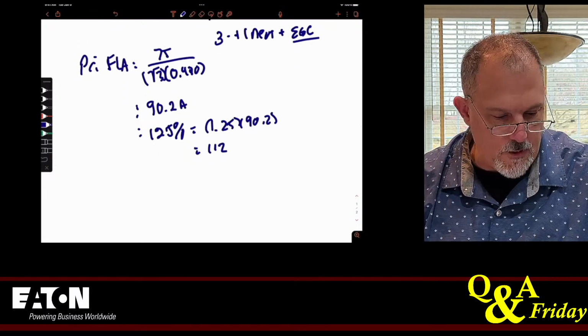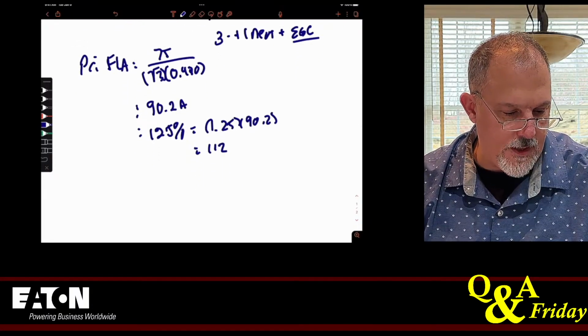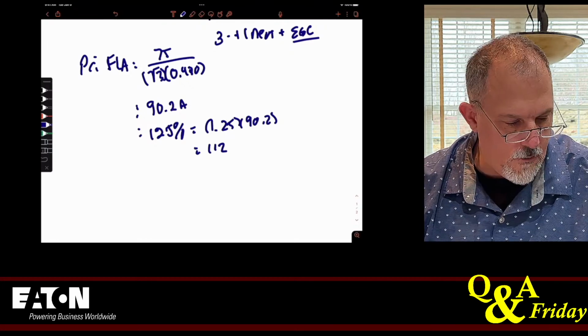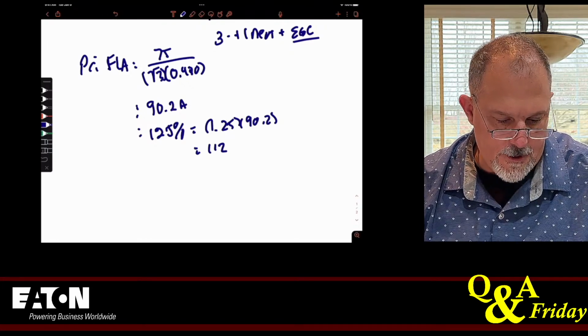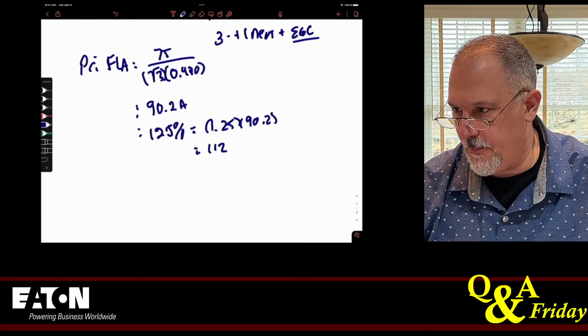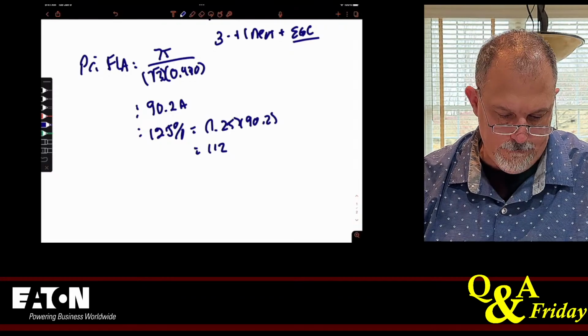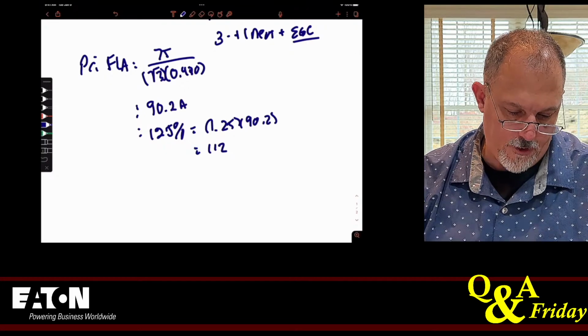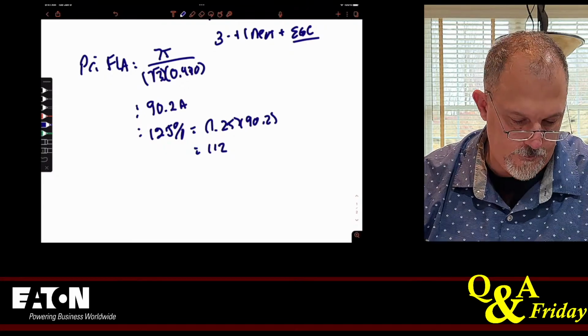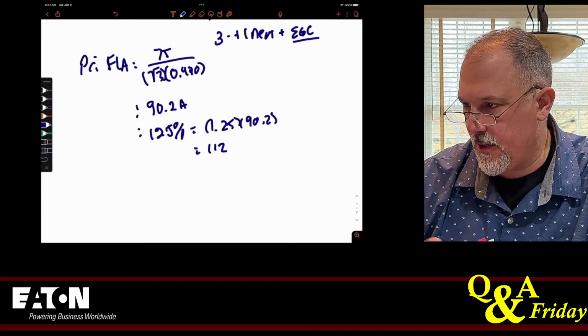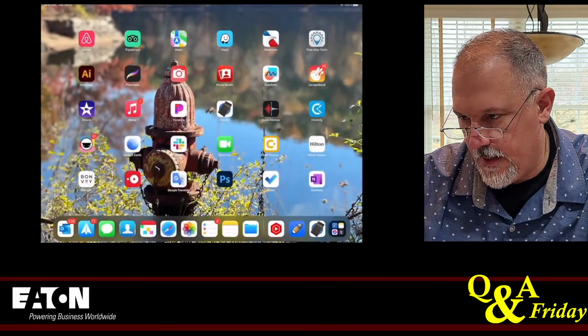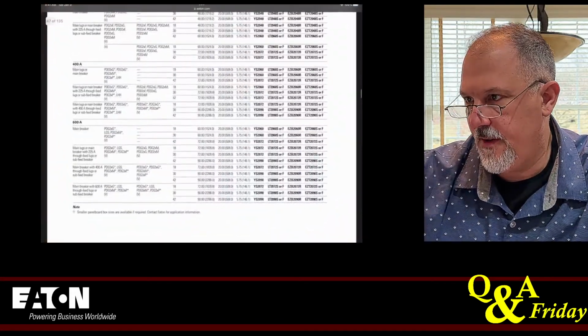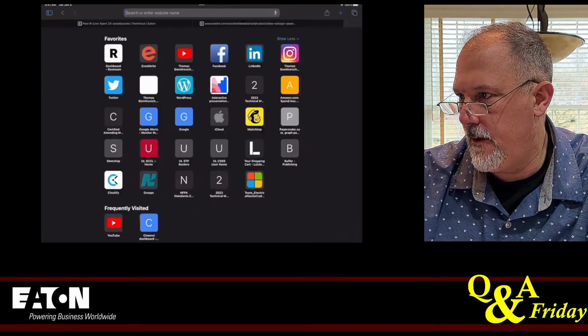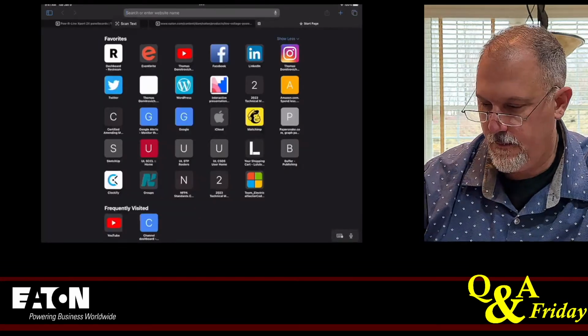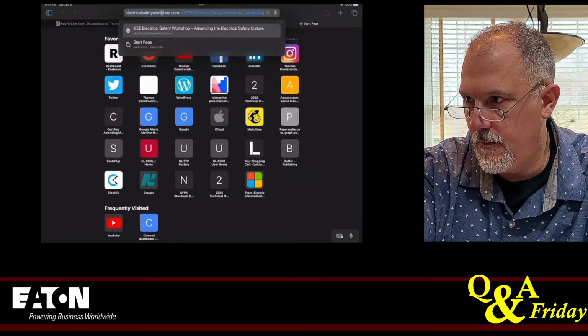What would I go to? Let's go back to Article 240 and see what my overcurrent protective device is. What are some standard ampere ratings? For 112, I can go to a 125 amp breaker or a 150 amp breaker. So I could put a 125 in there. Let's go to 125 amp breakers.